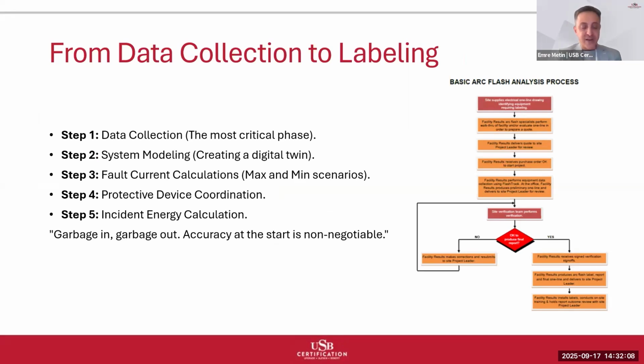Let me walk you through the complete arc flash analysis process, because understanding these steps helps you evaluate the quality of any analysis you receive and understand what information you need to provide. Step 1, data collection. This is absolutely the most critical phase, and it's often where analyses go wrong. We have a saying in engineering, garbage in, garbage out. The accuracy of your entire analysis depends on the quality of your input data. This includes complete electrical one-line diagrams, transformer nameplate data and impedances, conductor types, lengths and routing, protective device types, ratings and actual settings, load data for major equipment, and system grounding configuration.